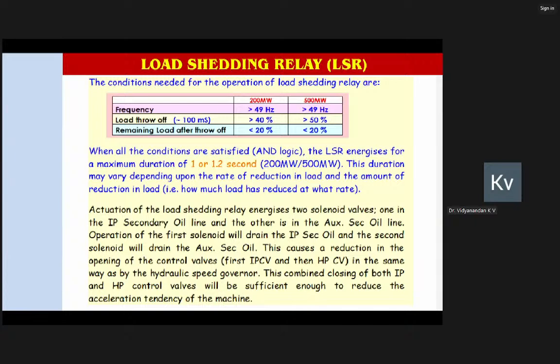In case of a 500 megawatt machine, there should be a sudden reduction in the electrical output by more than 50%. And after the reduction in the load, the remaining load should be less than 20%. If all these three conditions are fulfilled, then the load shedding relay will come into service. It will remain in service hardly for 1 to 1.2 seconds. And that time delay, how long the load shedding relay will remain in service, is not in our hand.